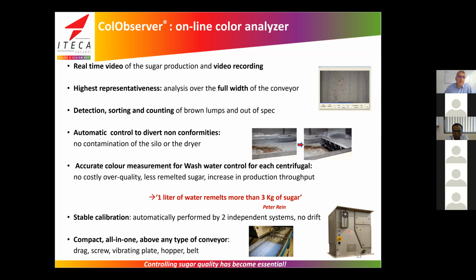To clean the window is very easy because you have just to push a button to say, I will clean the window. And automatically the system will open a flap to protect the sugar from the cleaning operation. An internal flap inside will open. And after, the customer just opens this door and cleans the window, and cleans the reference plate, because inside we have a reference plate too. And after, close the door and push a button, and automatically the protective flap will go back to let the system run again.